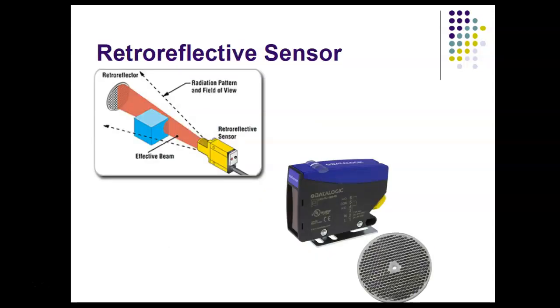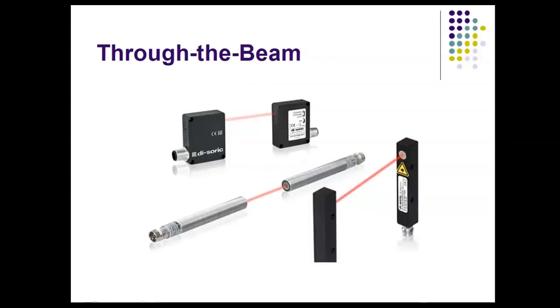Then we have what we call a retroreflective sensor. The problem with through-the-beam is the alignment has to be pretty precise, because we're using a narrow beam of light rather than a big one, since that would change the resolution. So you have to align these things pretty precisely before they work.